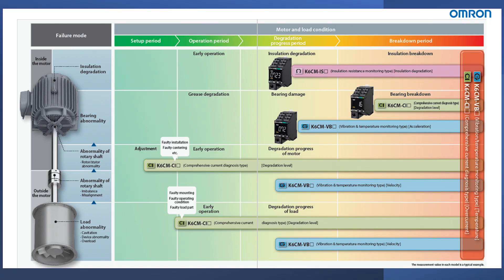On top of that we have sensors which can detect surface temperature and vibration. One other advantage we can exploit with motors is checking insulation resistance — which can break down and cause risk of electric shock and damage. Traditionally this was quite difficult: the motor had to be taken out of service, disconnected, and a skilled engineer would put a megohmmeter across each phase applying typically a thousand volts. It's now possible with modern IoT-based sensors to do this in real time. As long as the motor is not running, we can inject 50 volts on some models, or use a CT on others — allowing checks almost on an hourly basis. With the K6CM we can detect all these issues, analyze them on-site, and report back into your factory maintenance system.